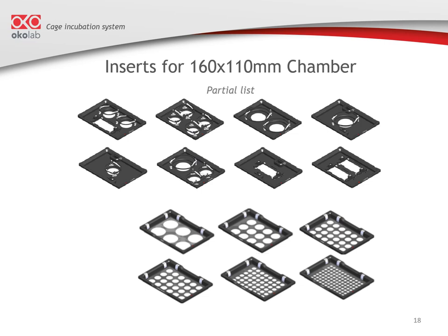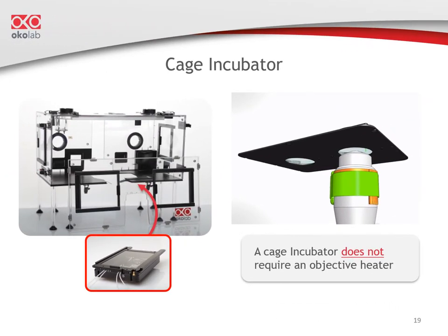This slide shows a partial list of available inserts. When imaging multi-well plates with a cage incubation system, you will always use an open frame, shown in the blue box. You don't need the perforated metal plate because the microenvironmental chamber, the stage, and the nose piece are inside the enclosure at 37 degrees. Additionally, you never need an objective heater because the objective and nose piece are inside the enclosure at 37 degrees.